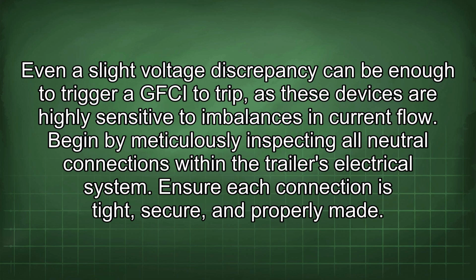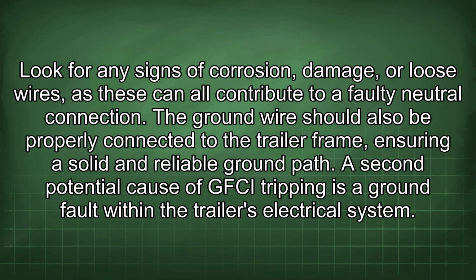Begin by meticulously inspecting all neutral connections within the trailer's electrical system. Ensure each connection is tight, secure, and properly made. Look for any signs of corrosion, damage, or loose wires, as these can all contribute to a faulty neutral connection. The ground wire should also be properly connected to the trailer frame, ensuring a solid and reliable ground path.